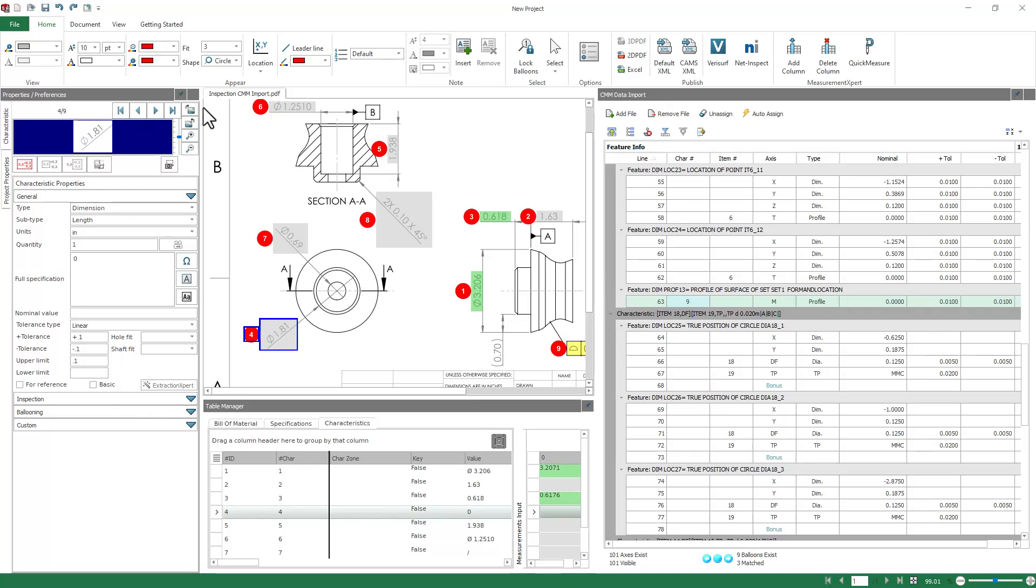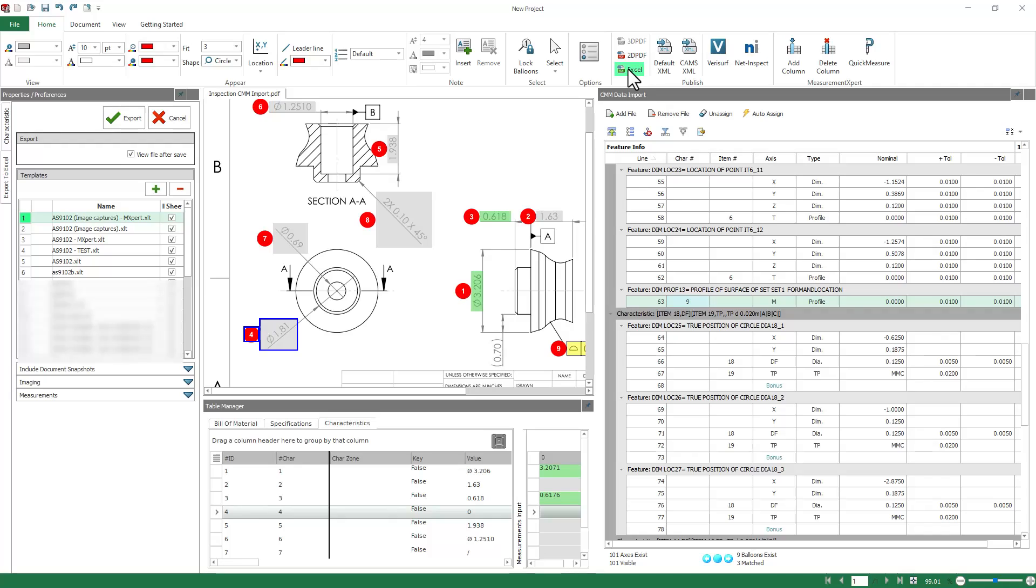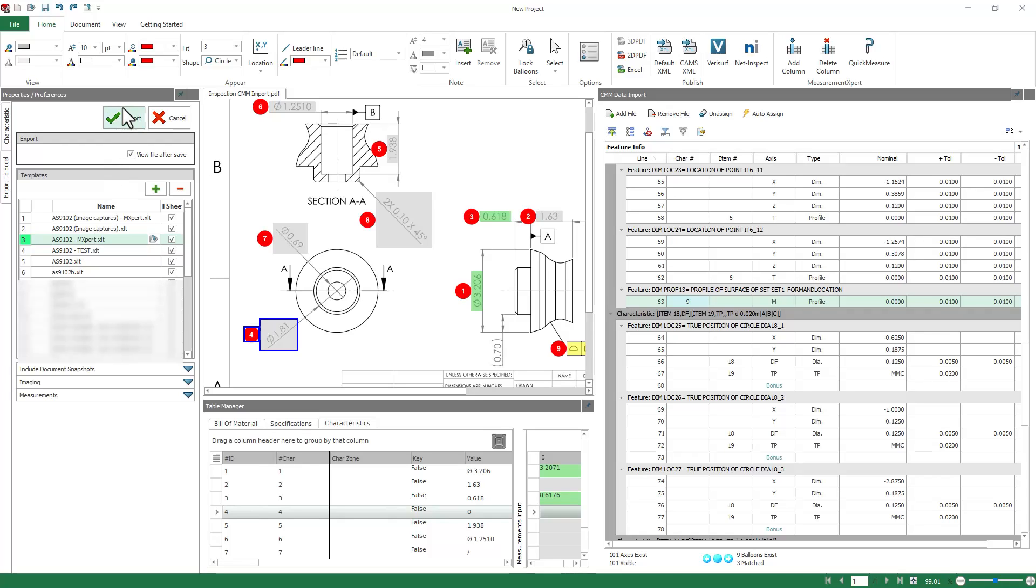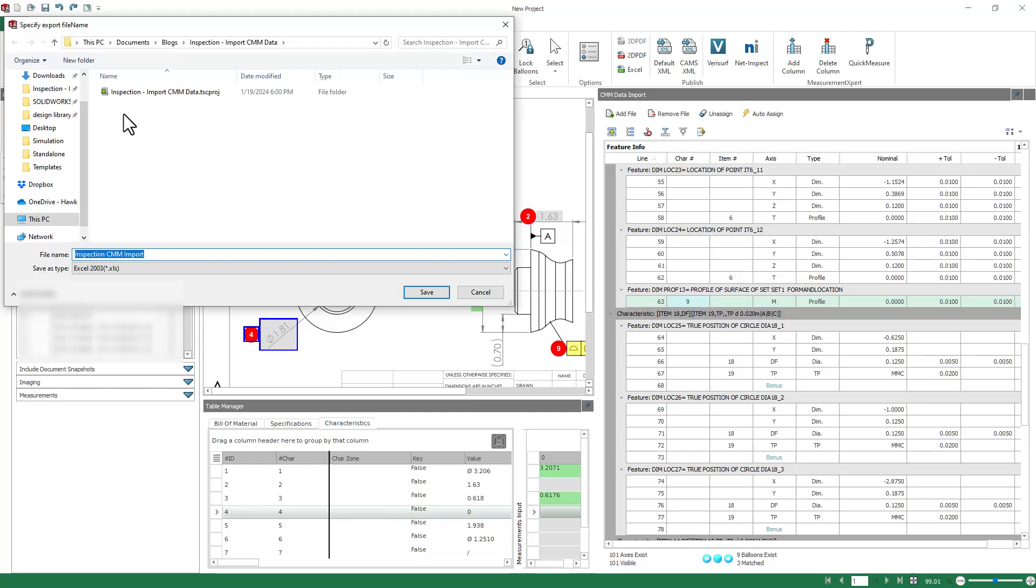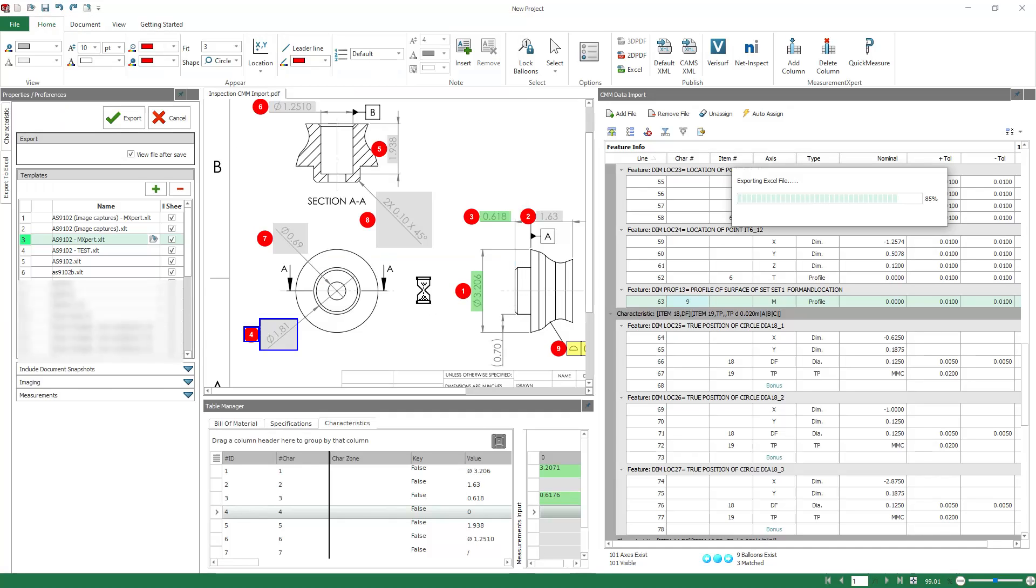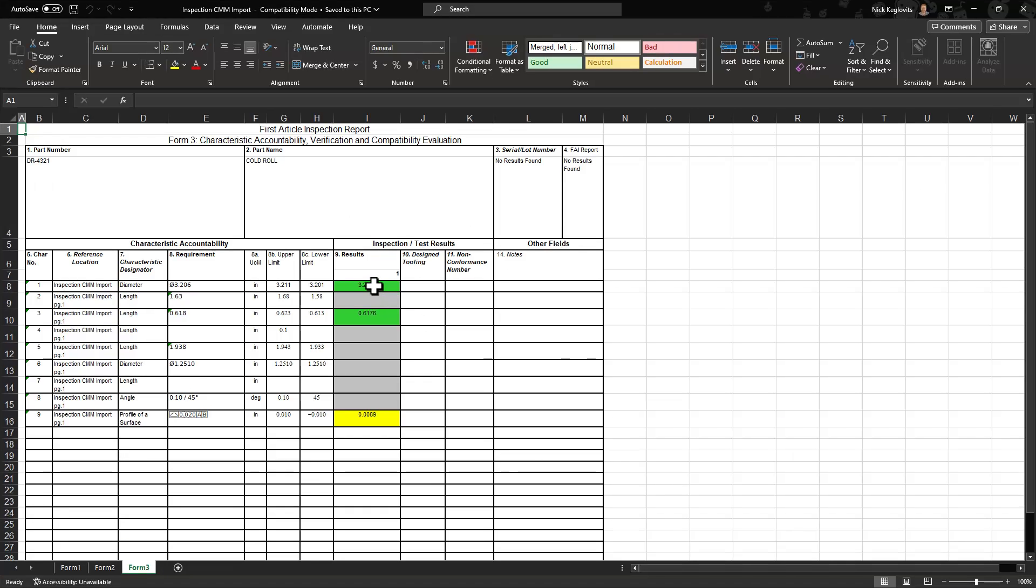So after the data's been assigned, you can go ahead and export your Excel report. Make sure you're using an M-Expert template, or basically a template that's been pre-configured with measurement tokens. And we'll hit Export, and save it in some folder. And you'll see that the measurement values are brought in where the measurement tokens appear in your template.